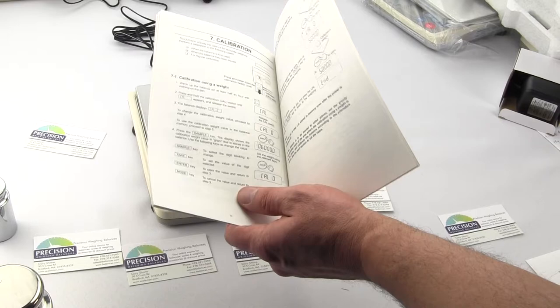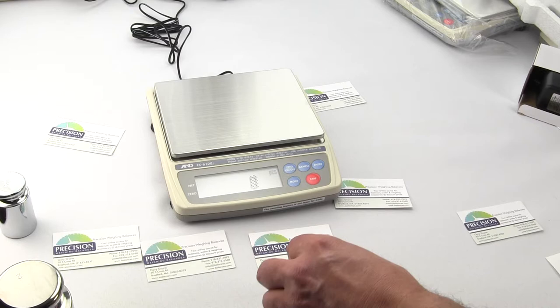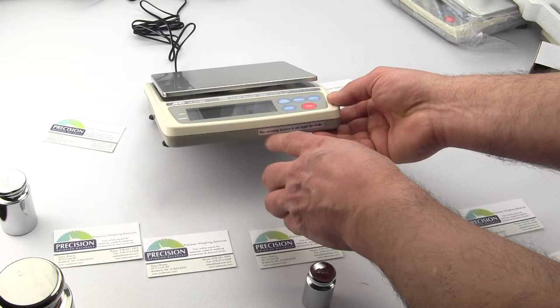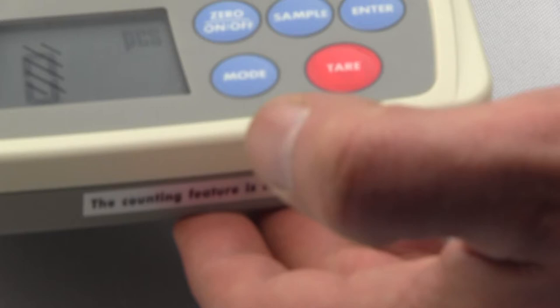You'll notice also on the front of the scale since this is legal for trade the very front there is a sticker saying the counting feature is not legal for trade. This needs to be on the scale as part of the requirements for NTEP approval. So that sticker can't be removed if you are using this for a legal for trade application.